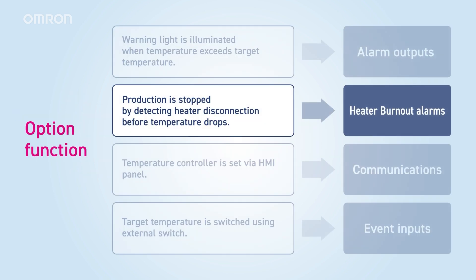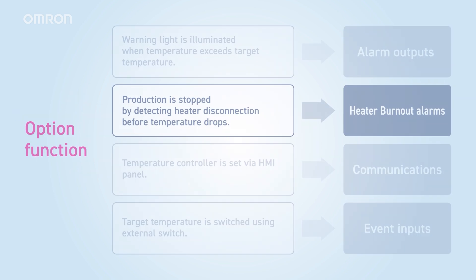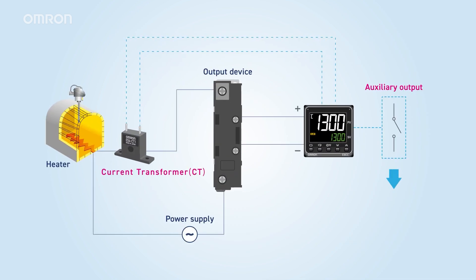Next, look at the heater burnout alarms. The current flowing to the heater is measured by a current transformer, and in the event of a heater burnout, an alarm is output via a relay signal from the auxiliary output terminal. This system detects heater burnout early, allowing the equipment to be stopped in time to prevent defective products.